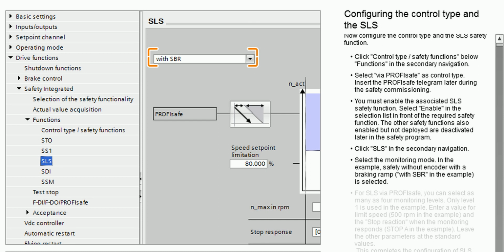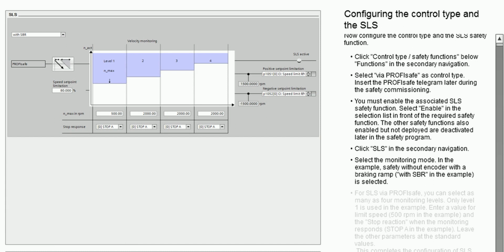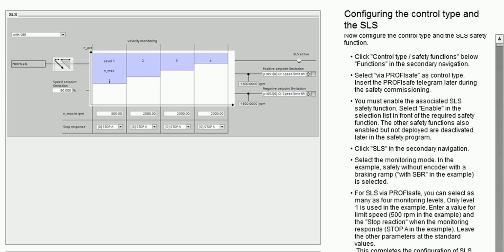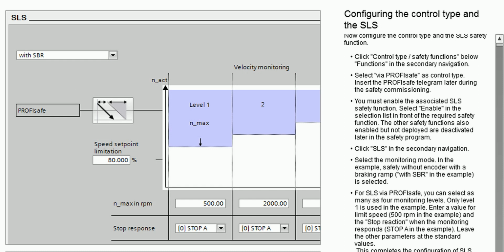Select the monitoring mode. In the example, safety without encoder with a braking ramp, with SBR, is selected. For SLS via PROFIsafe, you can select as many as 4 monitoring levels. Only level 1 is used in the example.